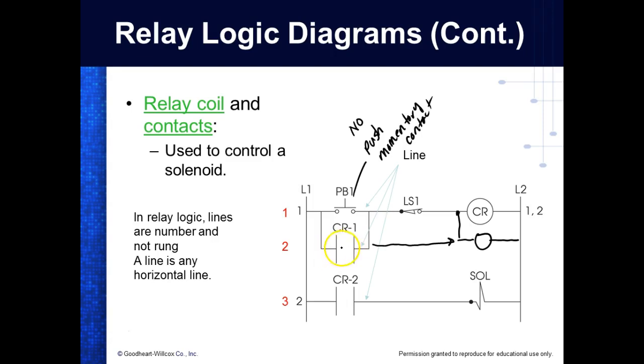This is drawn real big - usually we don't do it that big. What we do is come over here and give our relays a name, so this is wrong too. We give these things a name, and what they've done here is put the name inside the coil. If the name doesn't fit inside the coil, they'll put it down at the bottom. Then all the contacts controlled by that relay have the same name. That's what we're going to do in PLCs - they call it symbols, Siemens calls them tags, same thing. This is where you go in and assign these things a name, and from then on you can reference it by name instead of by address, which is pretty neat.